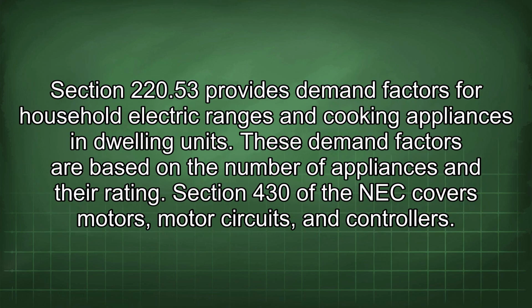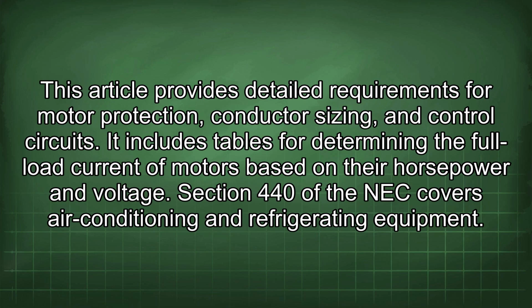Section 220.53 provides demand factors for household electric ranges and cooking appliances in dwelling units. These demand factors are based on the number of appliances and their rating. Section 430 of the NEC covers motors, motor circuits, and controllers. This article provides detailed requirements for motor protection, conductor sizing, and control circuits. It includes tables for determining the full load current of motors based on their horsepower and voltage.